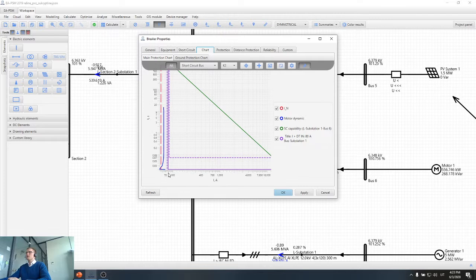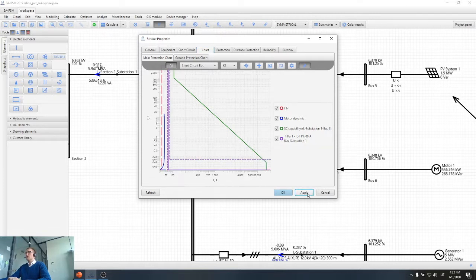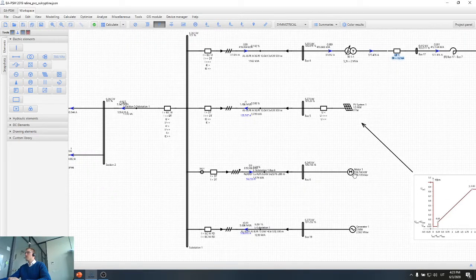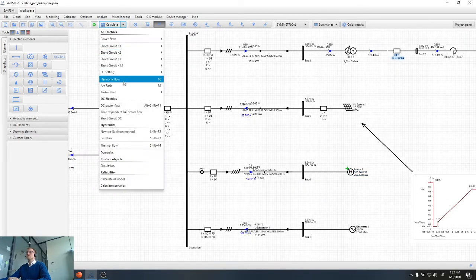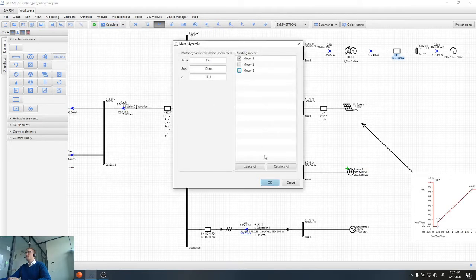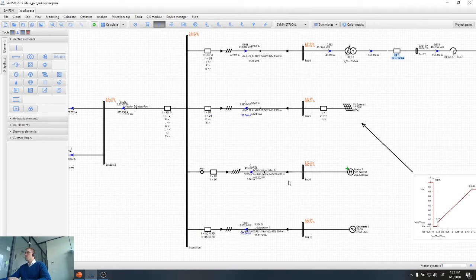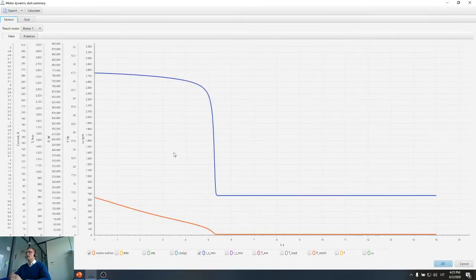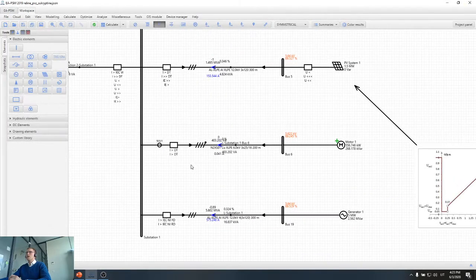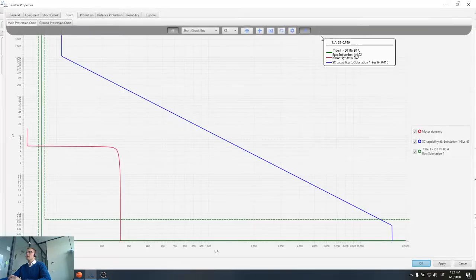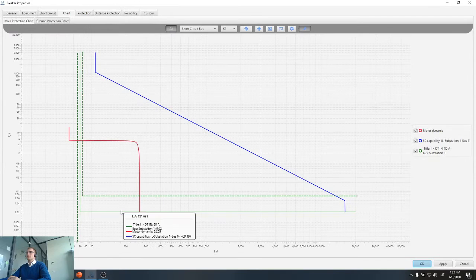So it's not good because it will not allow motor starting. You need to estimate what is the motor starting here. So let's calculate motor dynamics, motor starting, in order to estimate what is the motor starting time and motor starting current. So motor starting time we can see around 6 seconds, motor starting current around 263.